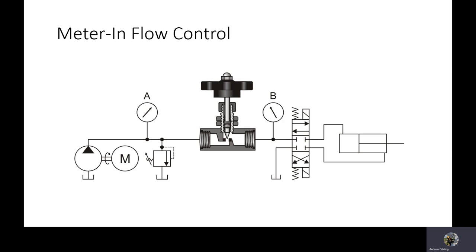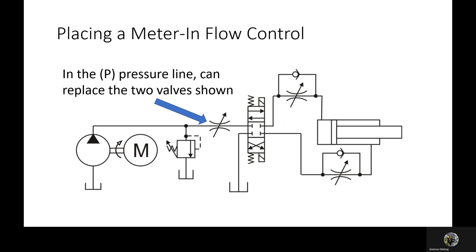However, because you're taking a nice laminar flow through the conductors and making it go through a passage and change directions, you're introducing some turbulence into the flow. As a result, you can get a little bit of a pressure drop. And if you have air and stuff in the system, these can be noisy too. This is where you'll hear it. Okay, this is pumping against a closed center, and as a result, the pressure would probably build enough that it would start to bleed off through my PRV to control the pressure ultimately in the system.